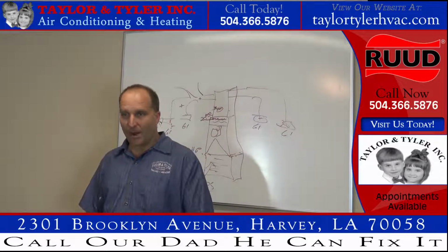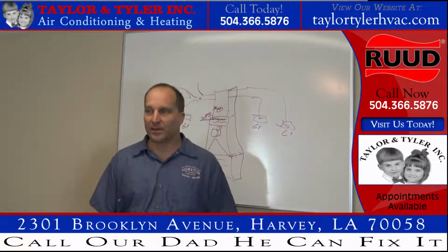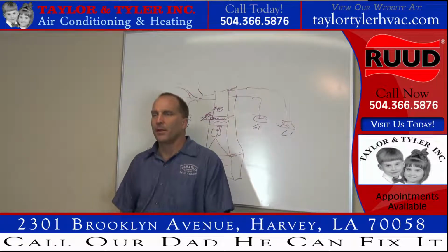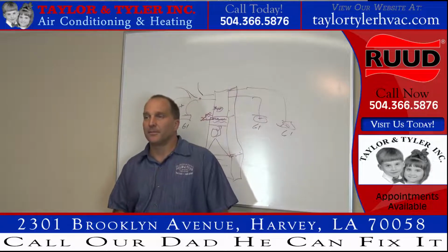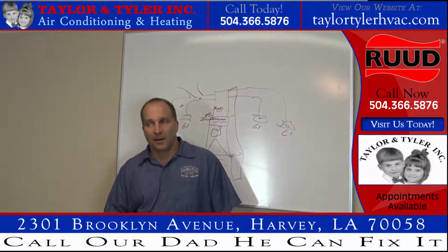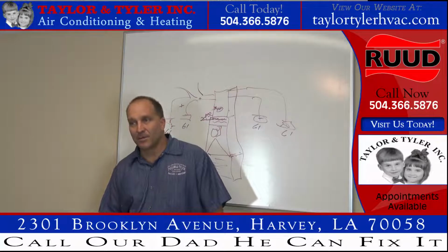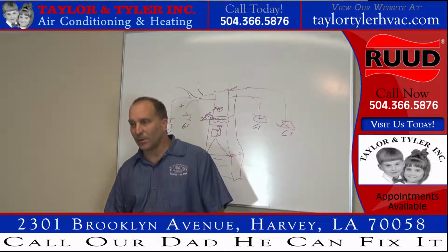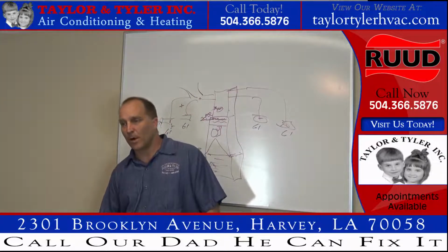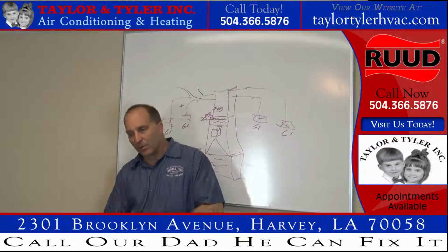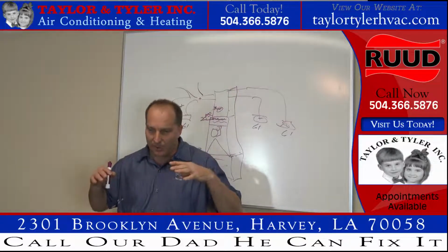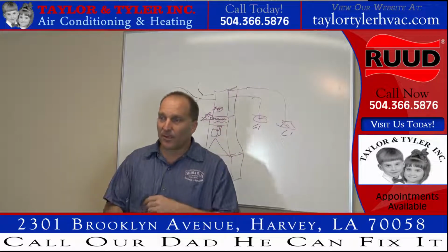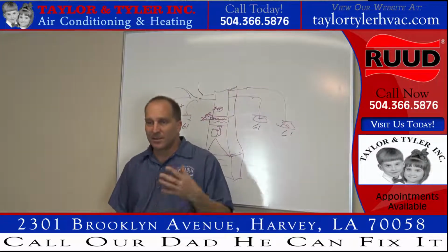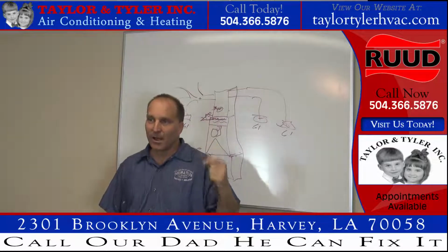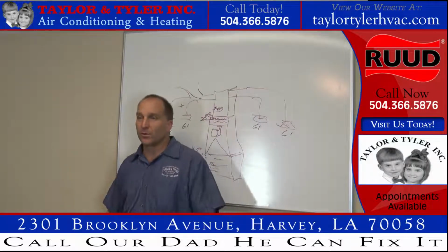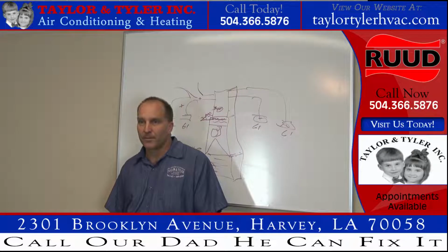So you go buy another TXV and put it in. You call me up and go, Eric, I put another TXV in. Same thing, man. My head pressure's high, my subcooling's high, so I lowered the refrigerant in the system. I made my subcooling proper. I put a new TXV in. I pulled a vacuum on the system. I made sure when I soldered the system in, everything's fine. I changed the dryer on the system. Same thing. Low suction pressure, high superheat. I'm not getting refrigerant through this system. I can't figure out why.